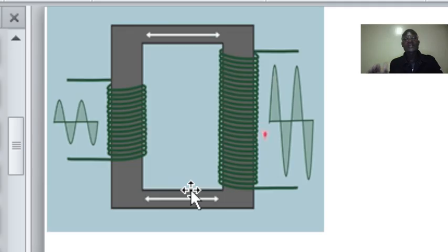For us to produce that X-ray, we need very high voltage that is able to burn the filament, to give us the thermal electrons, and then accelerate these electrons towards the anode. And also to make that anode more positive, we need power in terms of kilovolts. Now, what makes us achieve that kilovolts is the step-up transformer.